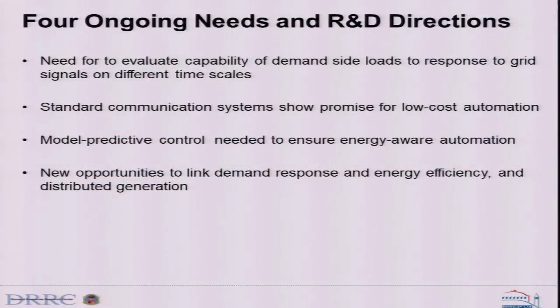There's a lot of challenges there on the architecture for these communicating systems. Model predictive control is needed for these energy-aware automation. We know we have to have real-time KW. That matters for energy efficiency, for demand response, for grid integration, and I didn't mention volt-var control. So conservation voltage reduction is coming, and we need to understand the loads in the building and the power factor issues associated with the loads as well.